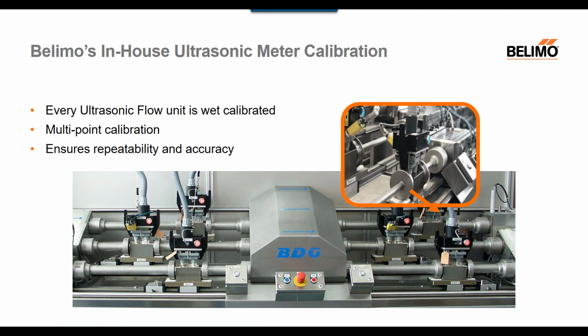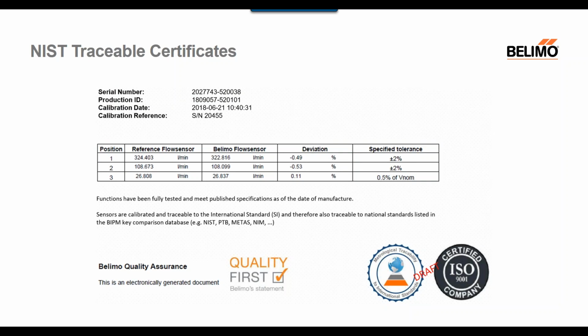The Belimo flow sensors undergo stringent step-by-step calibration processes. Each individual sensor is multi-point wet calibrated, ensuring optimum accuracy and repeatability, and simulates field installation. Calibration processes are performed using SI international standards and are traceable to NIST calibration standards. Individual NIST traceable calibration certificates are available for each flow sensor and are available through the Belimo Tech Support Team.